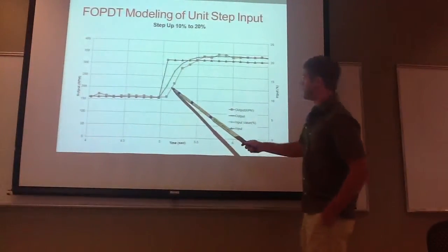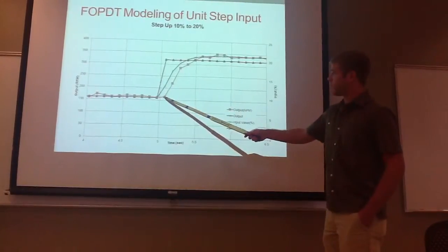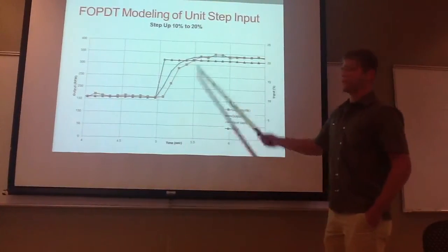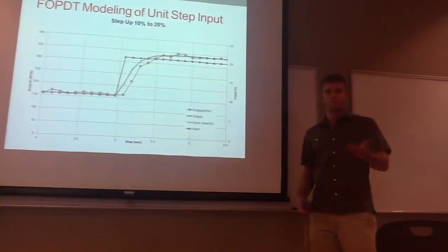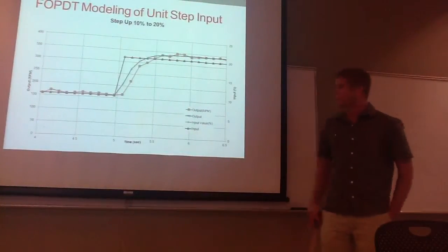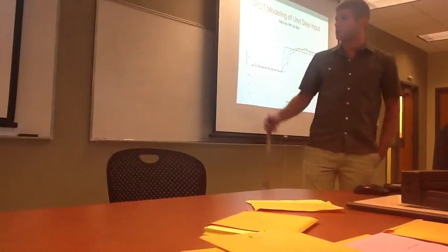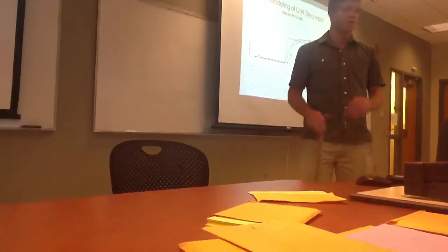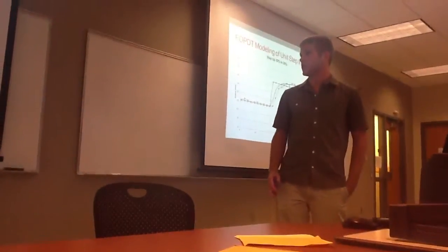In this case, you can see that the motor took a longer amount of time before it actually started to reach higher RPMs. This could be due to the actual resistance from spinning a mixer in the wastewater, or temperatures, or there could be an infinitely large number of variables.